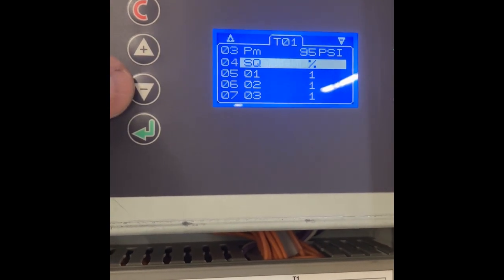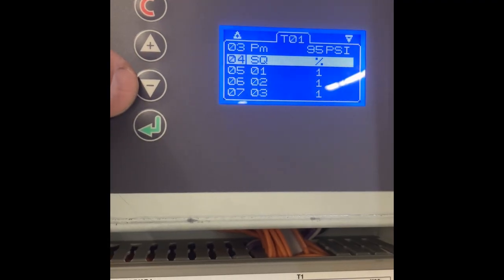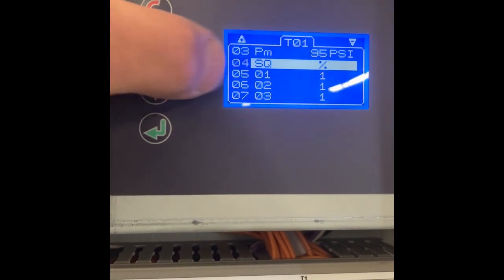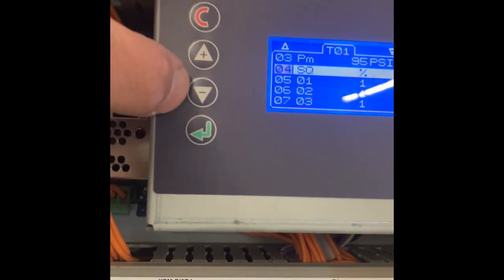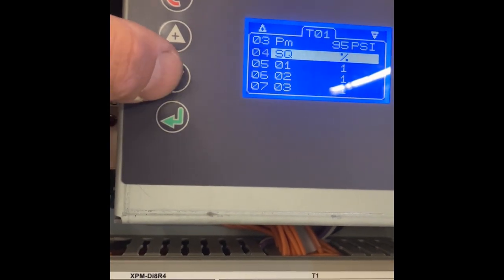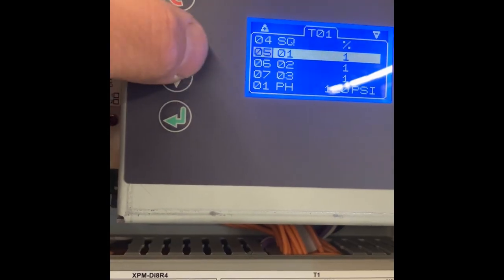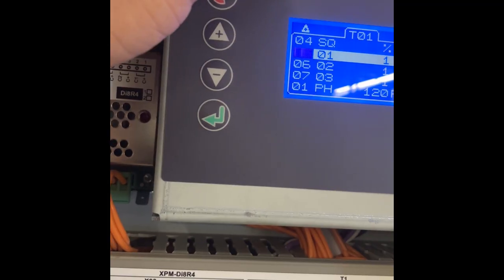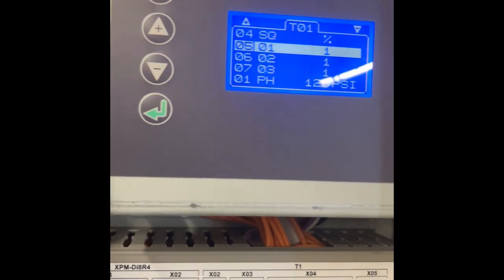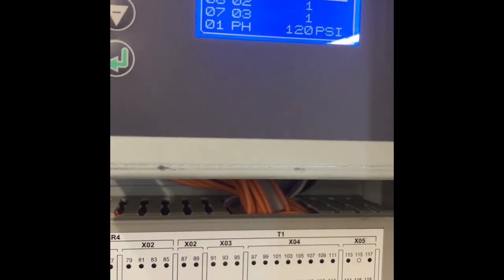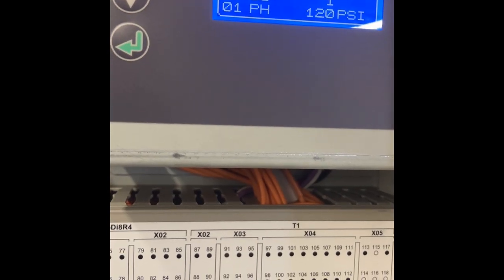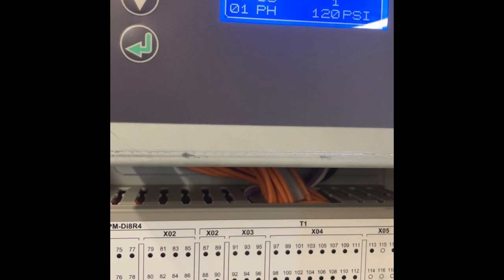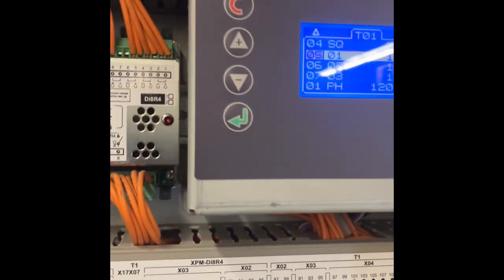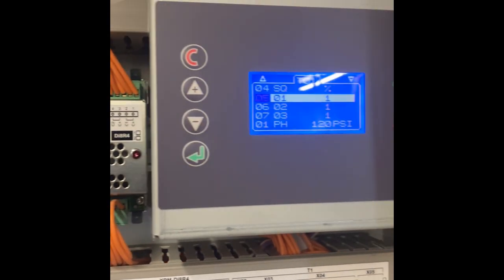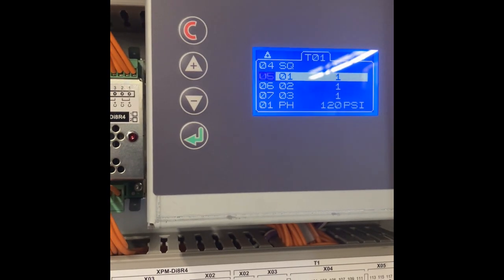This right here, you can set your sequence for schedule or for equal wear, or the percent sign here is for efficiency. I've usually found I get best performance out of these things if I set them for efficiency and make all compressors the same priority. There are certain setups where prioritization makes sense, or equal wear makes sense, but in this case we're just going for efficiency. So once you get to this point, you're pretty much set up for a basic system.